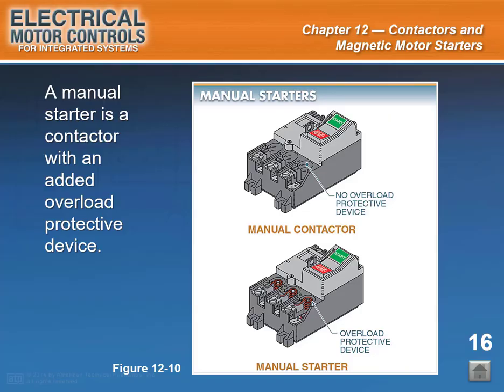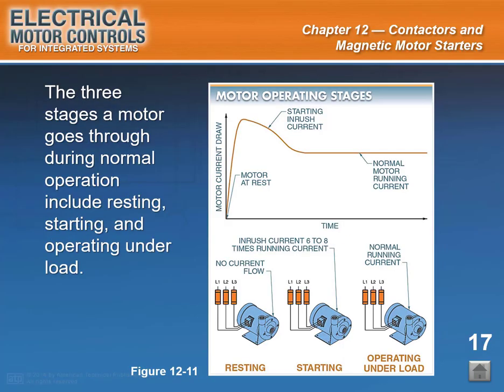Slide caption: a manual starter is a contactor with an added overload protective device. See figure 12-10. Manual starters are used only in electrical motor circuits. The primary difference between a manual contactor and a manual starter is the addition of an overload protective device. End of slide 16. Start of slide 17.